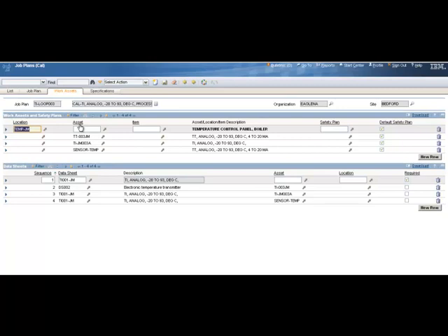If, for example, that loop calibration fails, then I have to find out what component within that loop was the failing component. By associating with the loop up here, the loop data sheet, I also associate each individual component's data sheet as well. And you notice that only one of these is required. The loop calibration has its own data sheets required. And we'll see in a little while when I do the work order for this that on the data sheet at the work order level, if I perform a calibration on the loop itself and those points are okay and it passes, I don't have to do the remaining data sheets. They're optional. But if the loop fails its calibration, then I have the other remaining data sheets there on the same work order. I can do each one, calibrate each individual component, and find a defective one much faster that way.